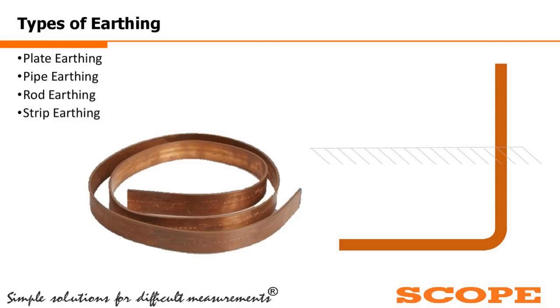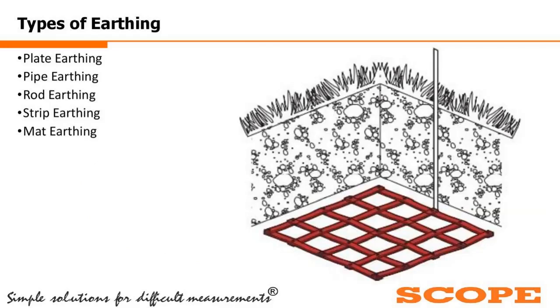First it goes down vertically, then after a certain depth it goes horizontally. The purpose is to increase the surface area for contact with the pure earth, so the basic purpose of earthing remains the same. Generally strip earthing is used in hilly terrain where there are rocks, or in transmission towers. The most common today is mat earthing, where copper strips are used to create a mat under the soil, and all the earth pits are connected to this copper mat, which lies at a certain depth below the surface. Whatever comes from any earth pit gets distributed, so the use of strip earthing is now much enhanced by creating a mat.